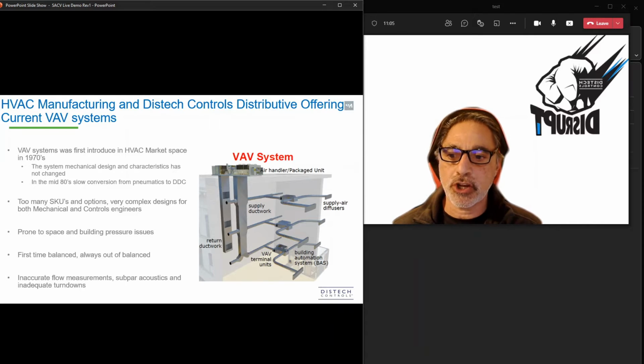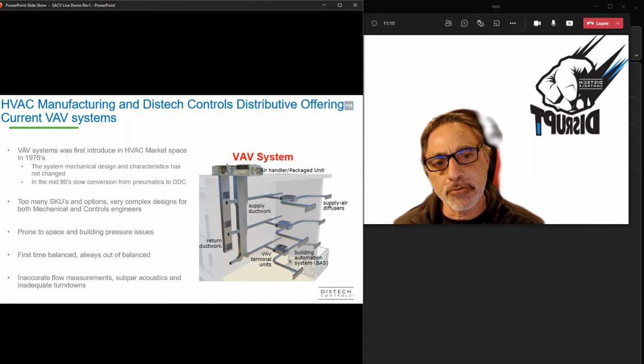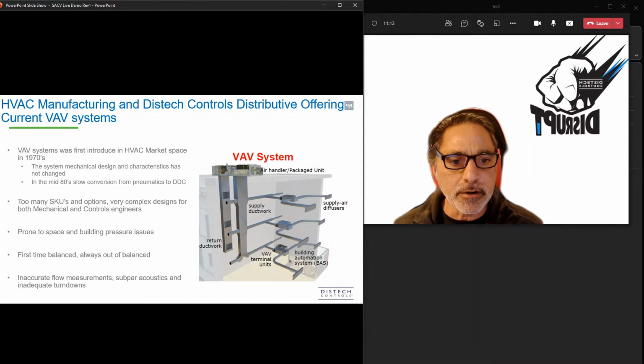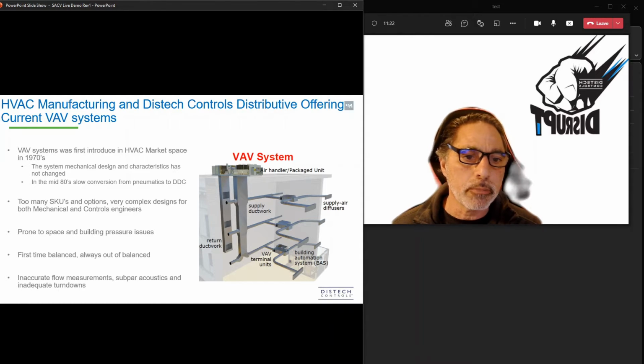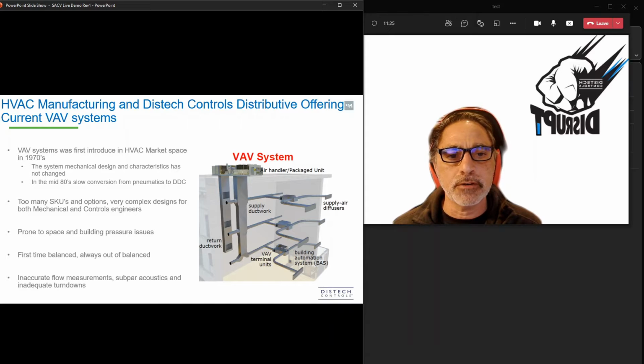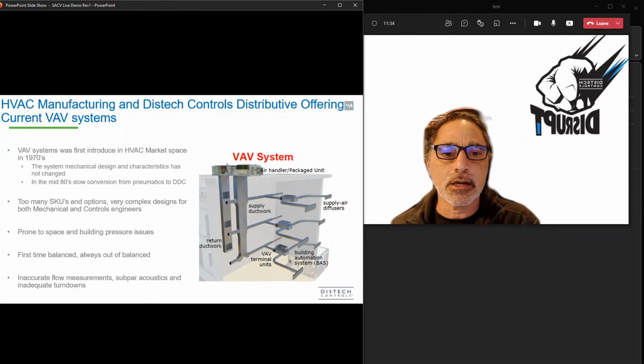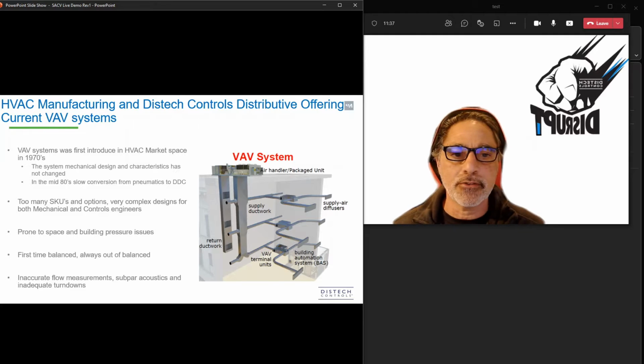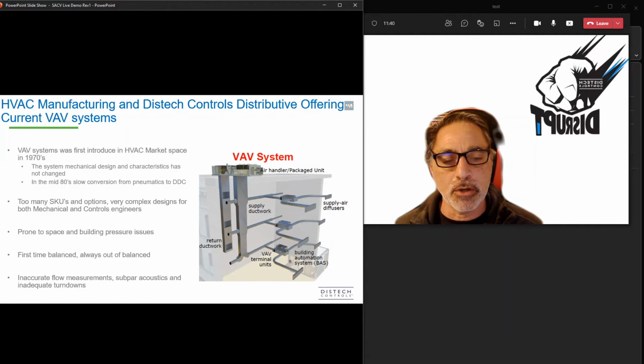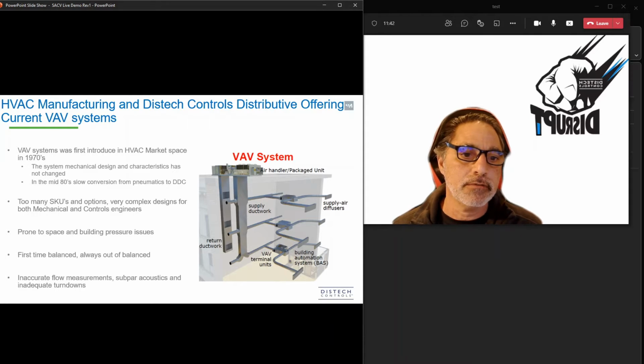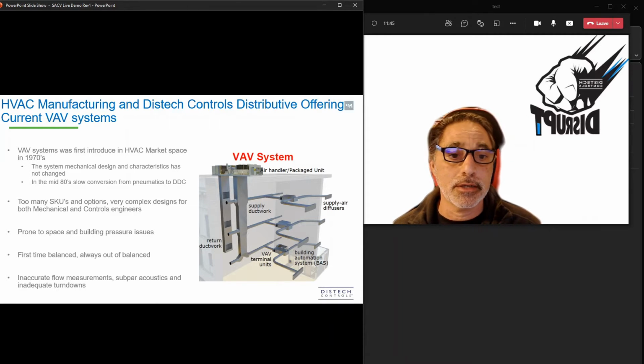So that's always been a challenge, and that's always been part of the workflow. There's also always been inaccurate flow measurement, and that is really where this new disruptive product is going to make a change. That is really about when you're on the lower part of the CFM and you're trying to manage the building in an unoccupied time frame, and you're really going after the ASHRAE standards that tell you when you're in that unoccupied time and you need to drive that CFM down to, let's say, 50 CFM or even below, there's not a single VAV system or VAV product out there today that can do that.